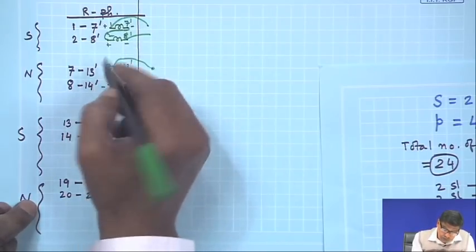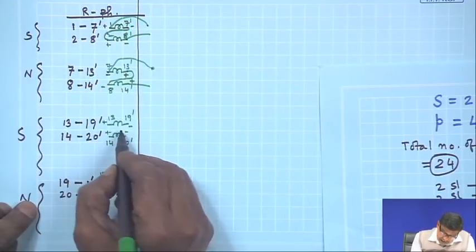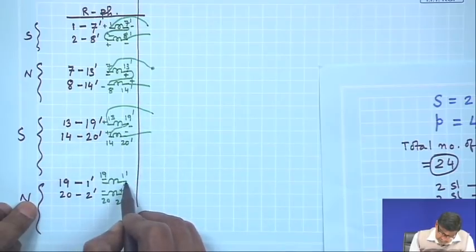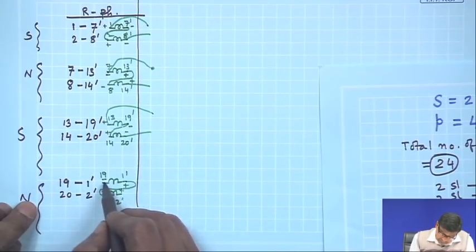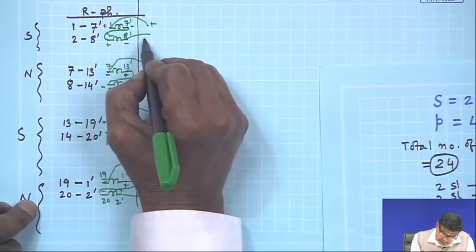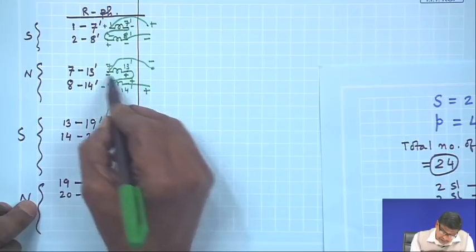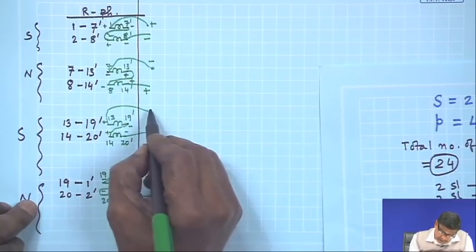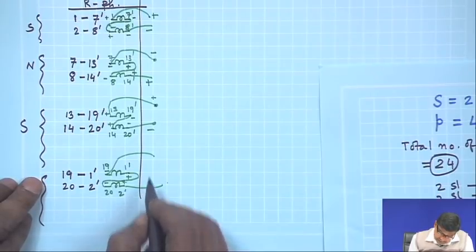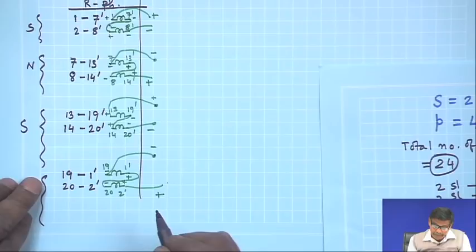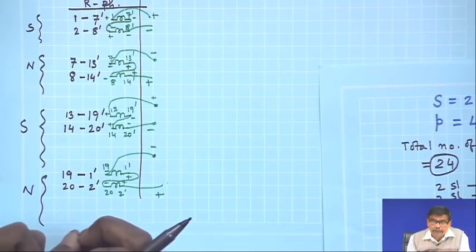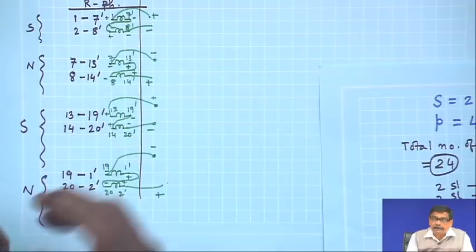These 4 groups are there for R phase only, and similarly these 2 in series, you get 2 terminals here, these 2 in series you connect. So, if you see the polarity of the group, this is plus, this is minus, this is minus, this is plus, minus plus, minus plus, and once again this is plus, this is minus, and last one is this is minus, this is plus. Each group will have same RMS voltages. To have 2 terminals of the R phase, all these coils should be connected in series.